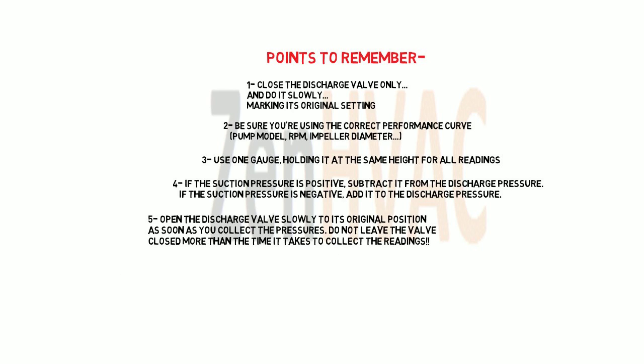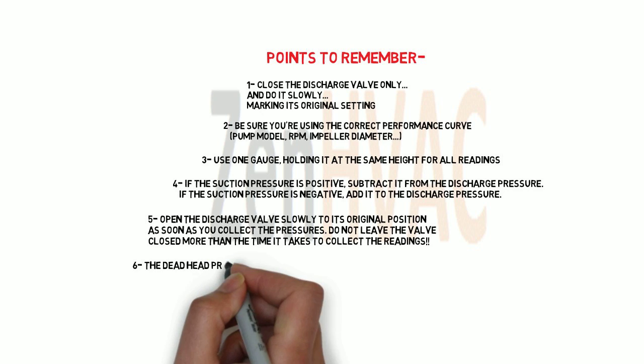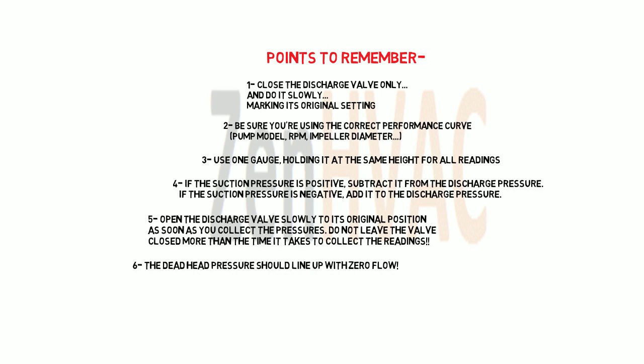Five, open the discharge valve slowly to its original position as soon as you get the pressures. Do not leave the pump deadheaded. It will damage the pump. Six, the deadhead pressure should line up with zero flow if the pump is operating properly.